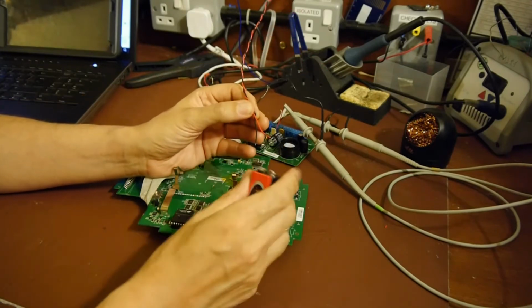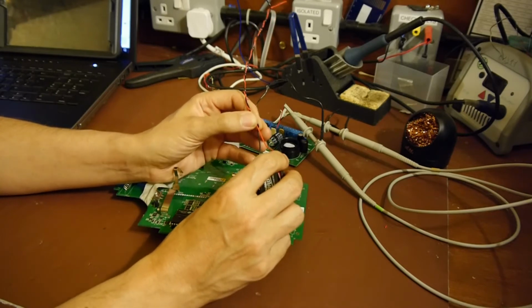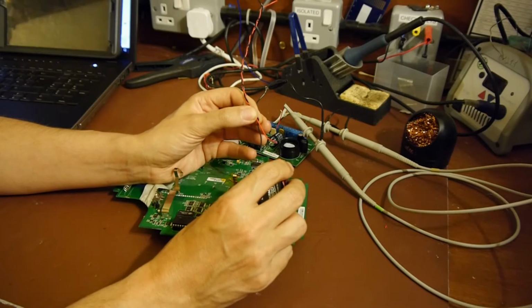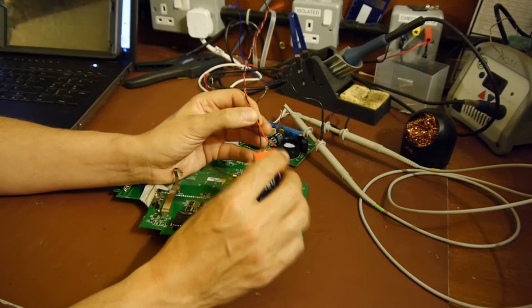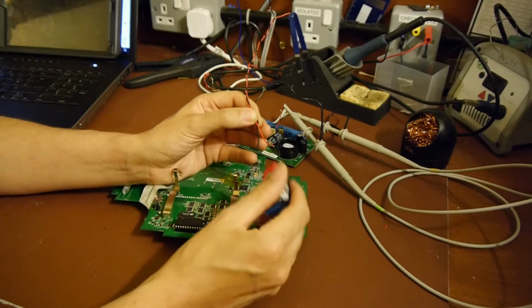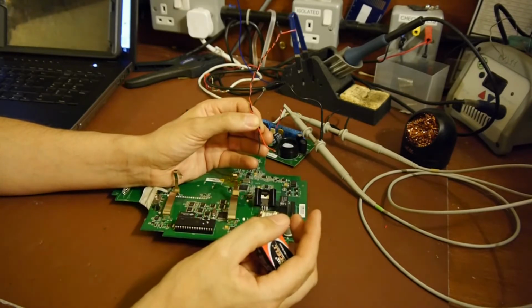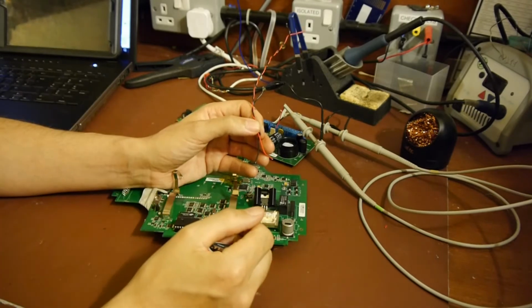What you could do to send a signal, you could put a battery on like that, and the lamp would come on. But what a differential system does is, for part of the signal, it will put the battery on that way, and then effectively it turns it around and puts it on that way. So basically it crosses the polarity, it swaps it, and the advantage of that is you get much better noise immunity.